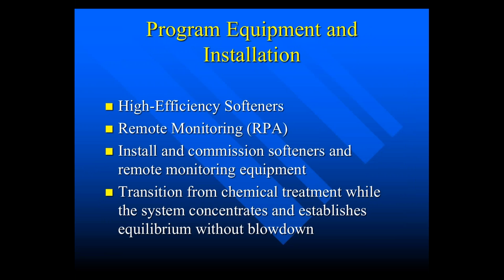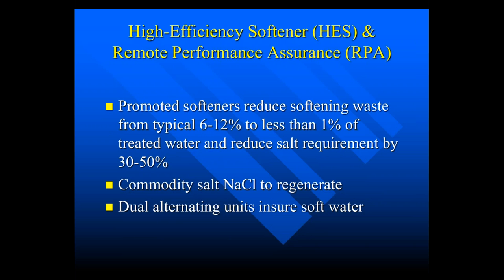The WCTI equipment includes high efficiency softeners and remote monitoring, which records both the water usage and the regeneration. They'll install and commission the softeners and transition regular treatment to zero blowdown treatment. Their high efficiency softeners reduce softening waste, typically 6 to 12 percent, and less than 1 percent of the treated water. They reduce the salt requirement by 30 to 50 percent. They use regular salt and they've got alternating softeners so that you've always got soft water supplied to the tower.